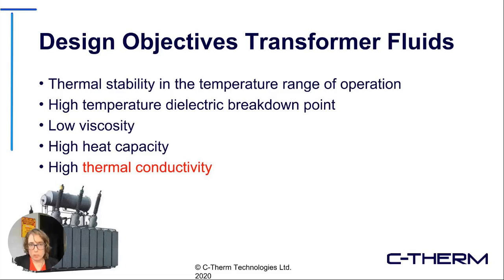It should also have a low viscosity, so it flows and convects well, improving its performance as a heat transfer fluid, and a high heat capacity, again to ensure good performance as a heat transfer fluid. It should also have high thermal conductivity, so that in parts of the transformer too physically constricted for passive convection to be efficient, you can still get good heat transfer away from sources of heat.